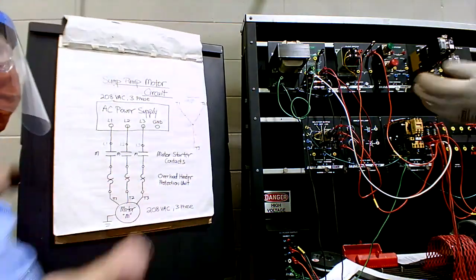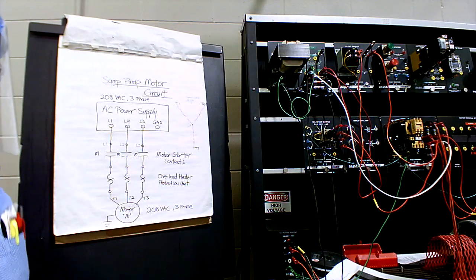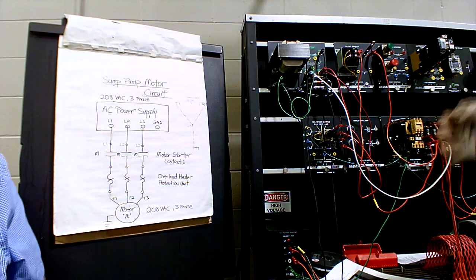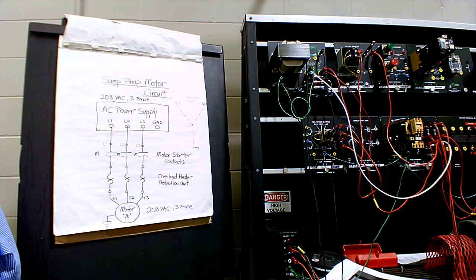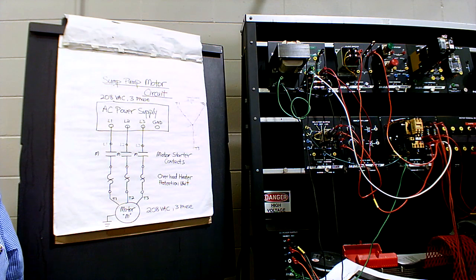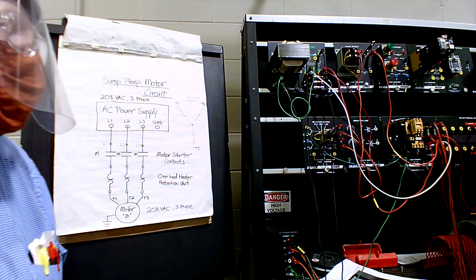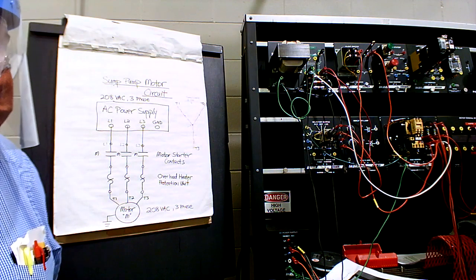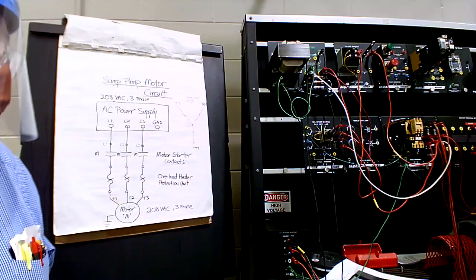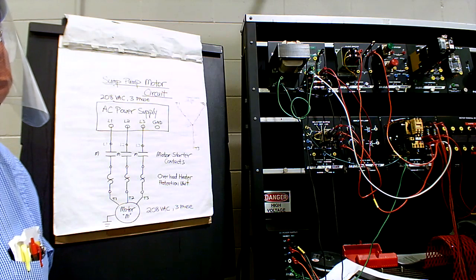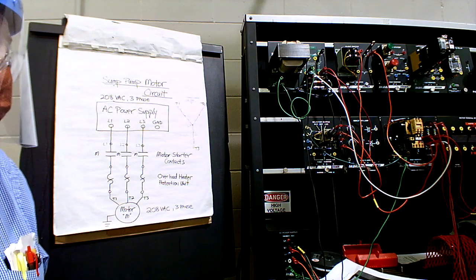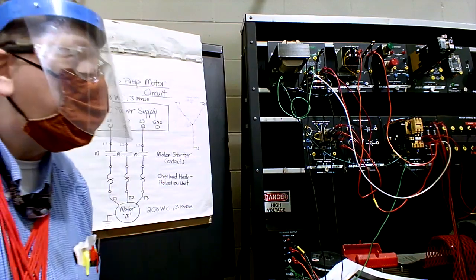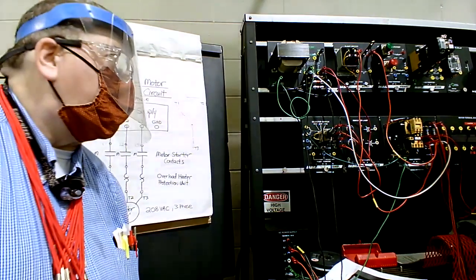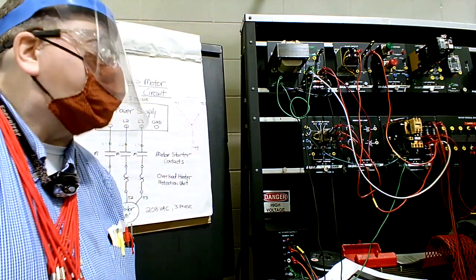Look, check your voltage, leg to leg and leg to ground, and then check the amps, and that'll be it. Then you take it apart. Somebody else can wire it up. Somebody else can have this board now, whoever needs something to do. So, tell me the numbers. Okay. And each leg to ground. Okay. Good. And now check your amps.